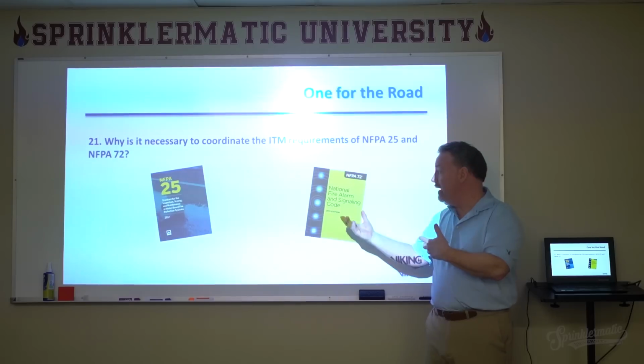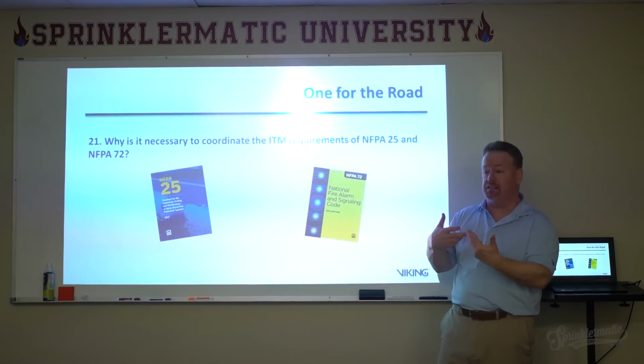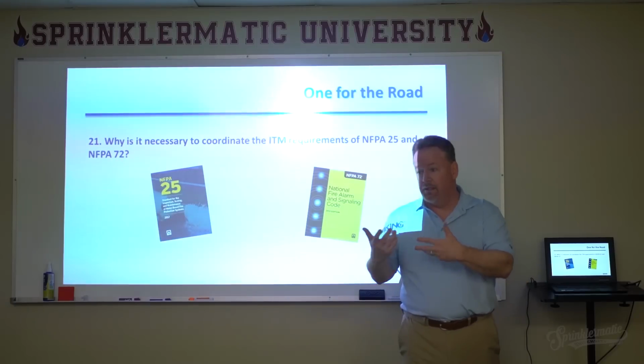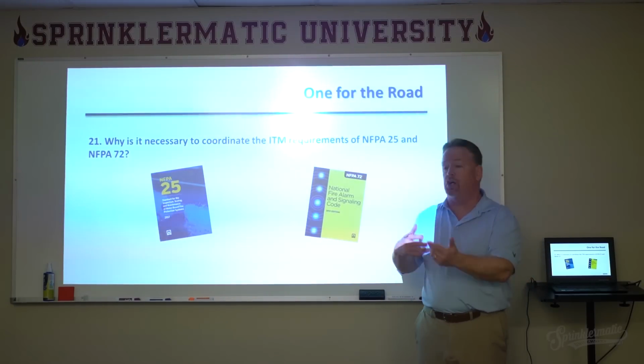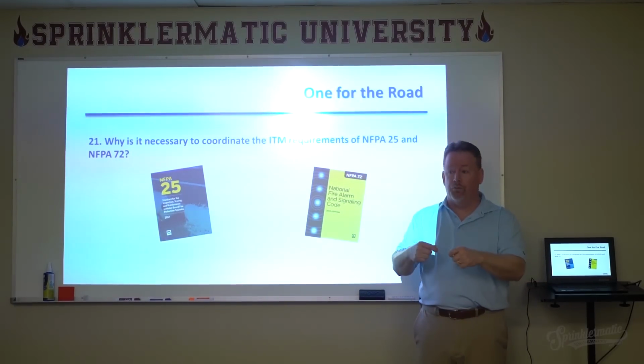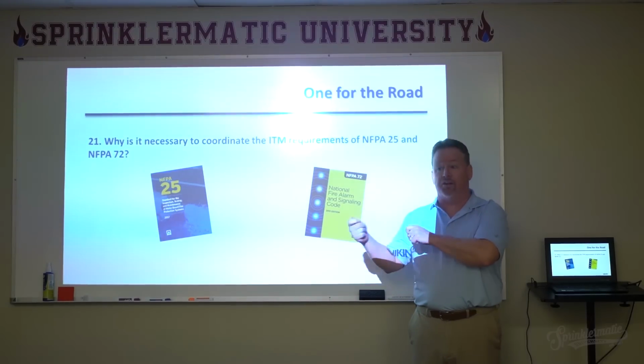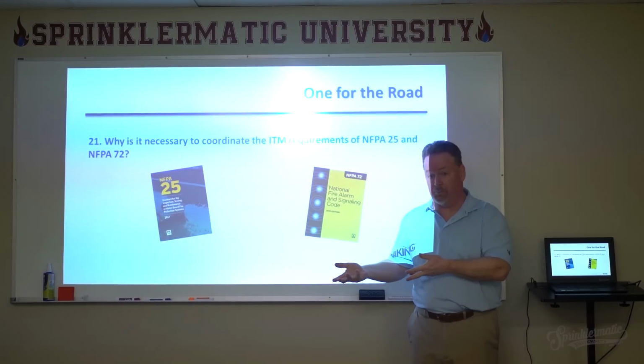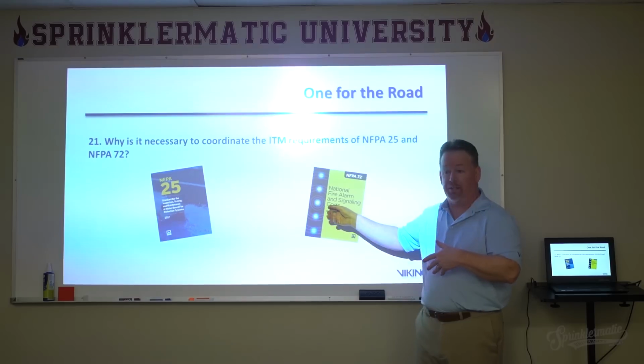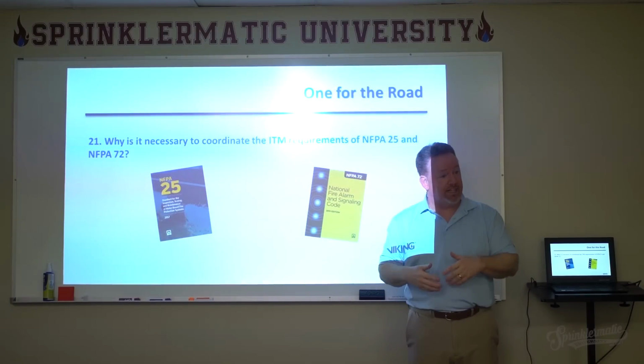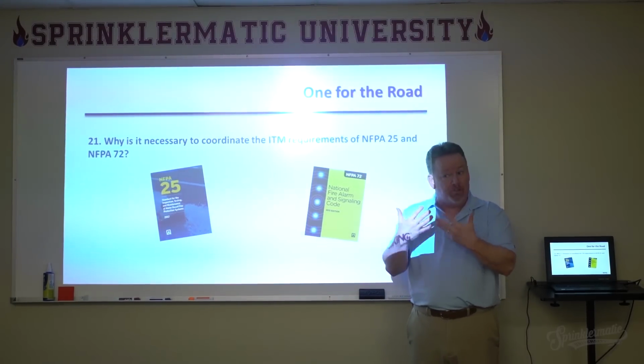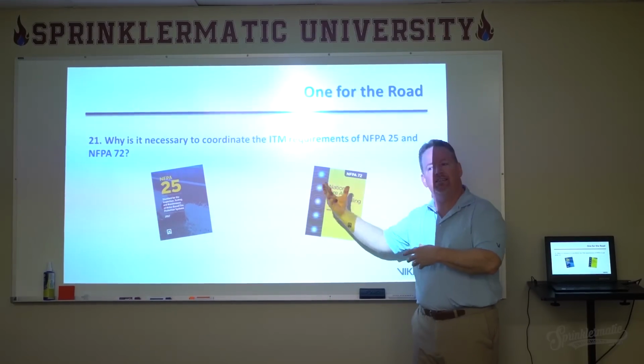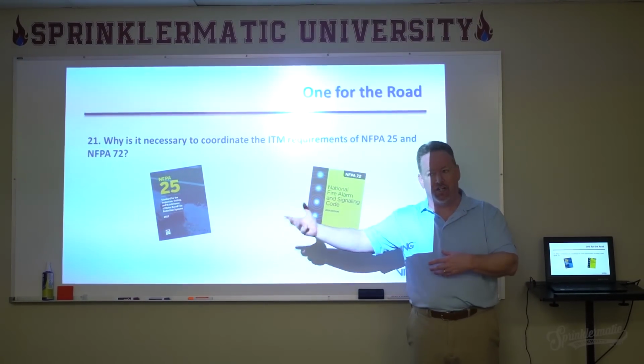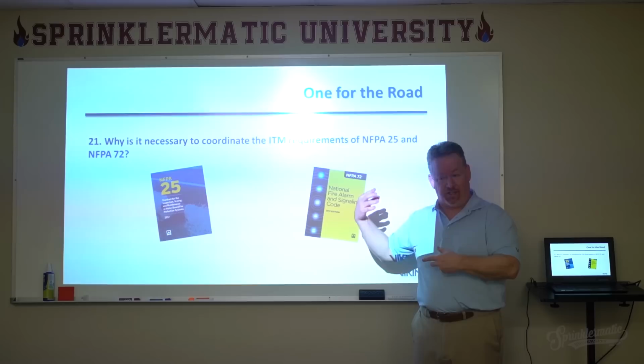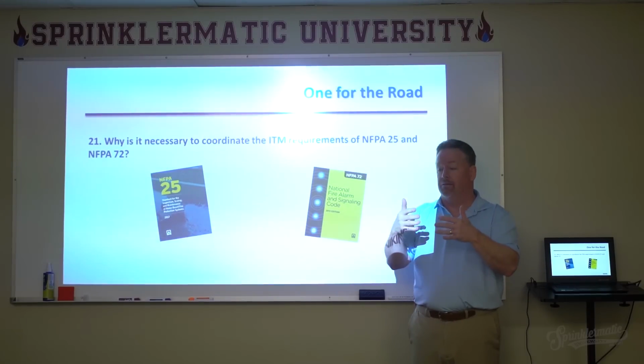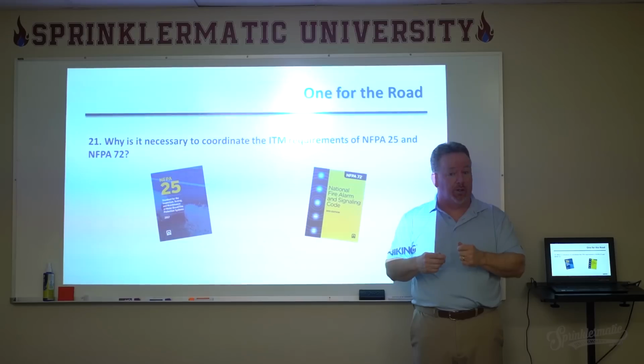NFPA 72 says that anytime an alarm system is installed in a building, one of the conditions it monitors is the condition of the fire sprinkler system. So it's mandated in NFPA 72 that these two systems link together. The challenge is they have slightly different positions and frequencies for dealing with these interactive components.